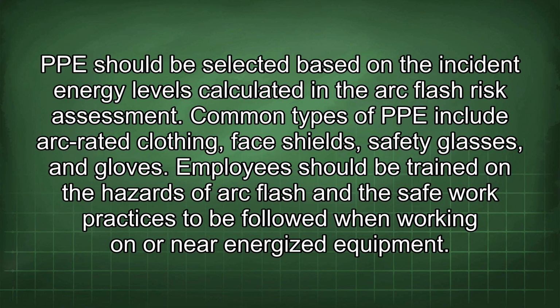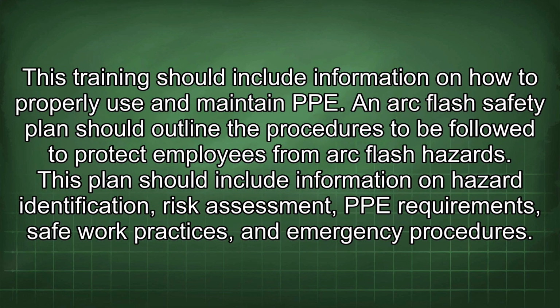PPE should be selected based on the incident energy levels calculated in the arc flash risk assessment. Common types of PPE include arc-rated clothing, face shields, safety glasses, and gloves. Employees should be trained on the hazards of arc flash and the safe work practices to be followed when working on or near energized equipment. This training should include information on how to properly use and maintain PPE.